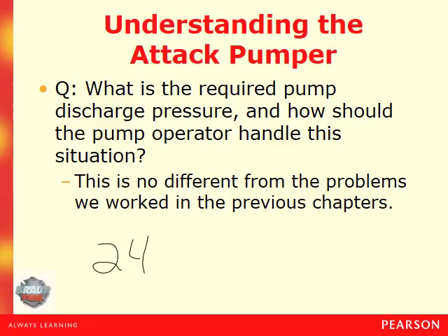Our gallons per minute are going to be 60, so we're still dividing that by 100, so that is 0.6. Again, that's squared. And then we're going to multiply that by our length of hose, which is 150. Of course, we divide that by 100, which gives us 1.5.